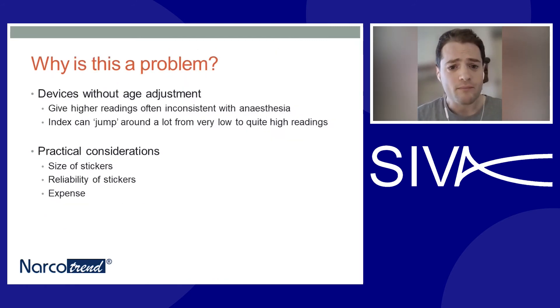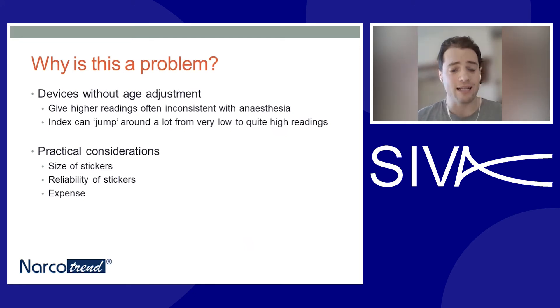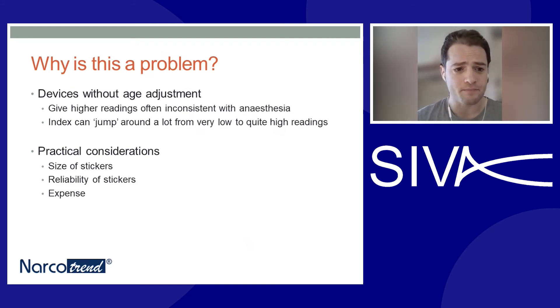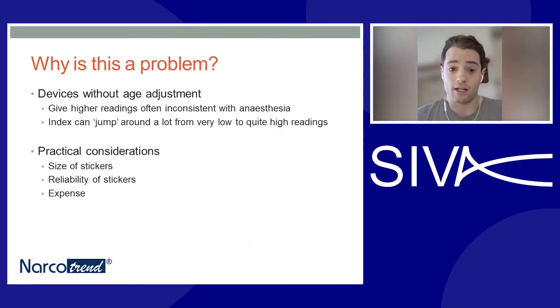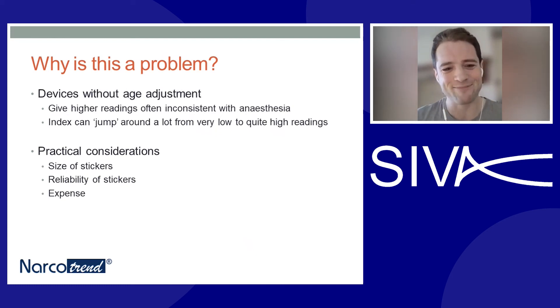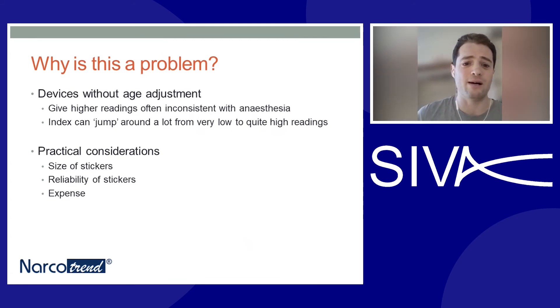So why is this a problem? Devices without age adjustment can often give quite high readings that are inconsistent with anaesthesia and out of keeping with the clinical picture of the child. The index value can also jump around a lot, switching from quite low to quite high readings without any particular clinical change in the child. There are also practical considerations: the size of stickers is often poorly designed for a child's head, leaving very little real estate space. The reliability of the stickers can be quite variable, sometimes requiring several attempts to get one that sits well. Finally, some paediatric stickers are more expensive than their adult counterparts, which is important to consider in the current economic environment.